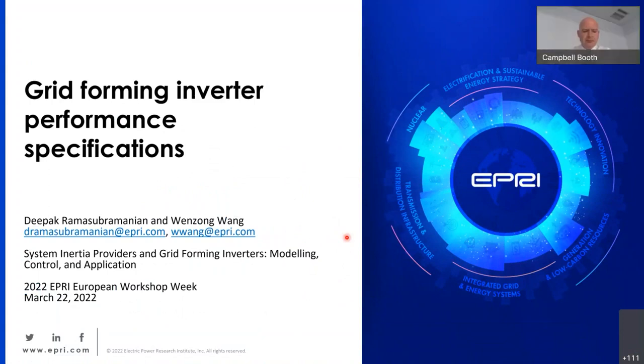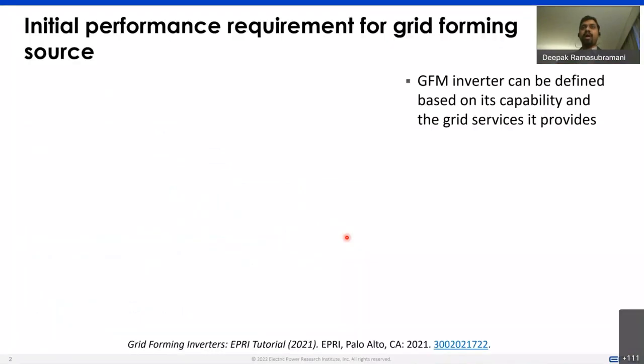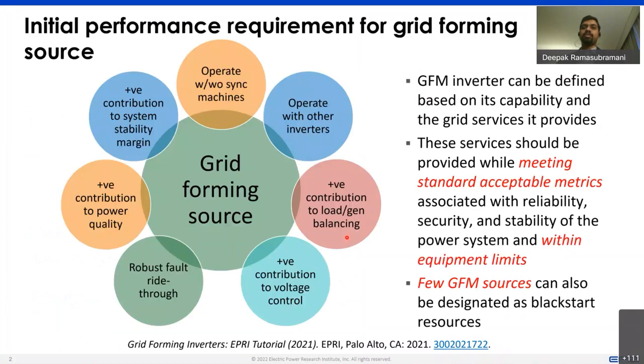Thanks, Campbell. As I mentioned, it's going to be a joint presentation between my colleague Wenzong and myself. And the way we are approaching grid forming inverters from an EPRI side is looking at it from the perspective of not necessarily voltage source versus current source. Those are critical behavioral characteristics that do play a role. But at the fundamental level, when we look at it from the system planner, system operator scenario, what we essentially want is a future inverter which can operate both with and without synchronous machines.